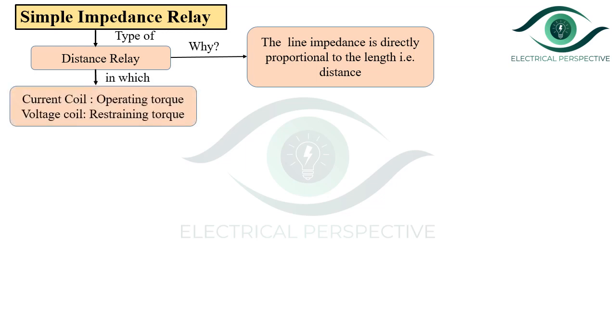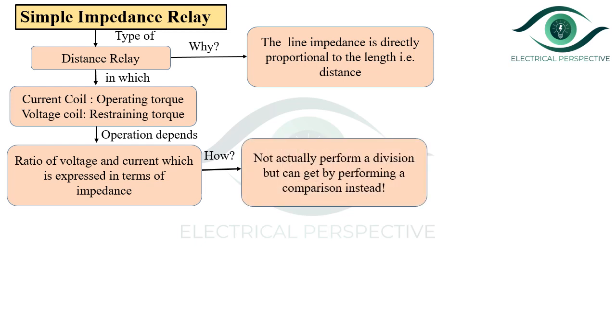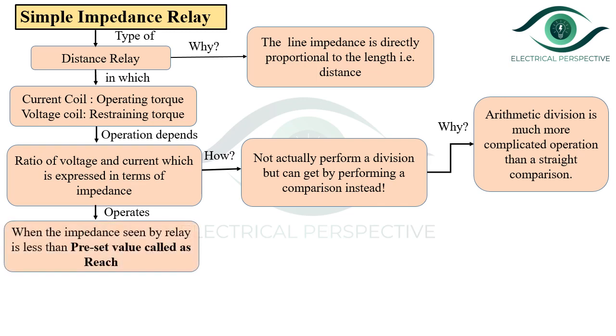The current coil provides the operating torque and the voltage coil provides the restraining torque, and its operation depends on the ratio of voltage and current, which is expressed in terms of impedance. To compute the impedance, there is no need to perform the actual division of V by I; we can get it by performing a comparison instead, because arithmetic division is a much more complicated operation than a straight comparison. The simple impedance relay operates when the impedance seen by the relay is less than the preset value called the reach.